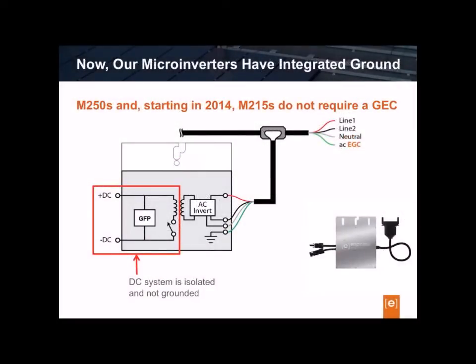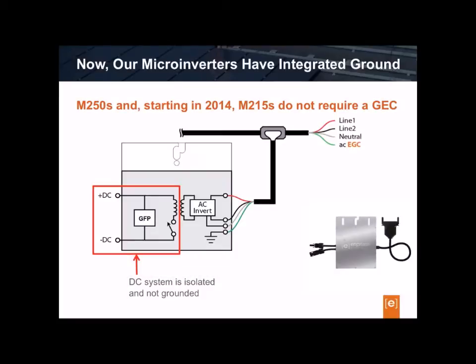Now all Enphase microinverters manufactured for use in North America feature integrated ground. By isolating the DC circuit, solar installers can build ungrounded photovoltaic arrays in accordance with NEC 690.35. Enphase microinverters with integrated ground can detect ground faults on either the DC positive or negative conductor of the PV module. Also new to these microinverters is the insulation monitor, or IM, which measures the insulation resistance of the DC circuit. These features offer greater safety than previously possible and allow for the removal of the separate GEC required for previous generation microinverters.